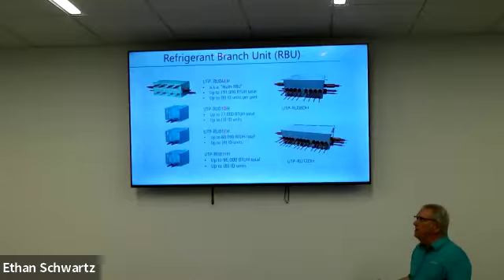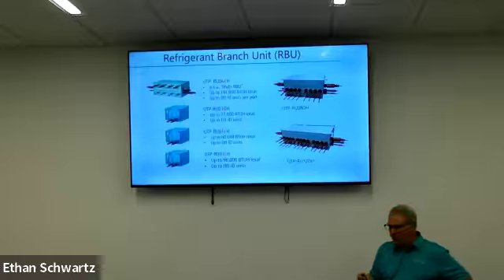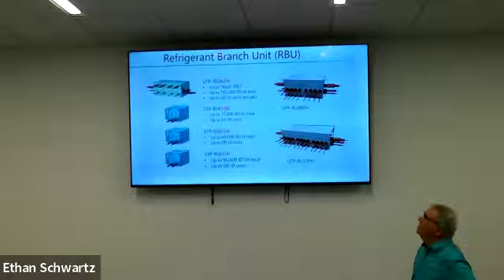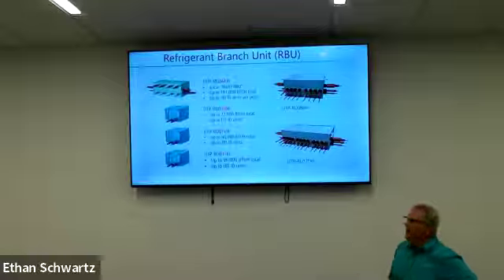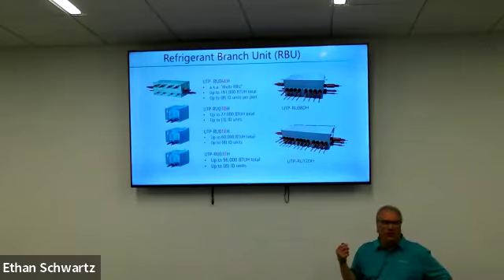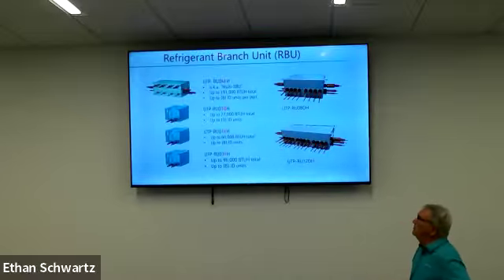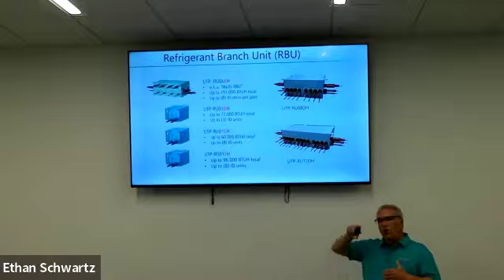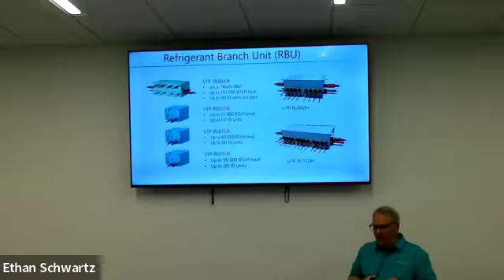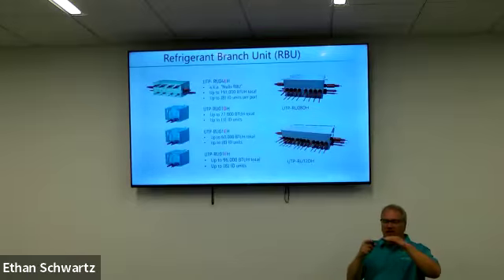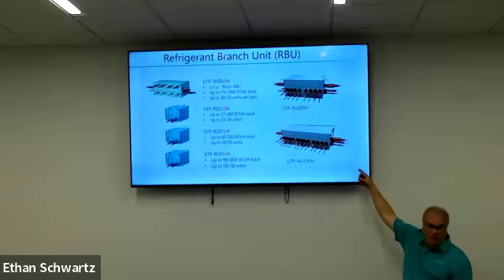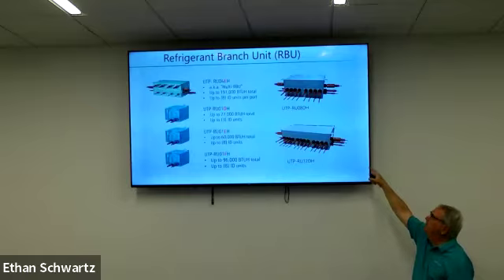So it just depends on the layout, and this is done with something called Design Simulator, which is a software. But all that I would like you to be aware of is that, okay, when you're talking to a contractor or the contractor is looking at a job with their customer, where am I going to put this third component? Kind of know where the outdoor units are going to go. We kind of know where the indoor units are going to go. Where's this fellow going to go? And where is that interconnected piping going to be routed? So those are all the same types of questions. And then if we're going to branch off, just like you saw when we were comparing the J series and the mini splits, we have the separation tubes. We will have 3 separation tubes in one heat recovery separation tube kit.